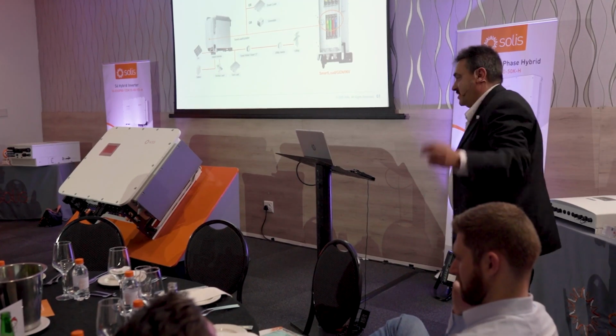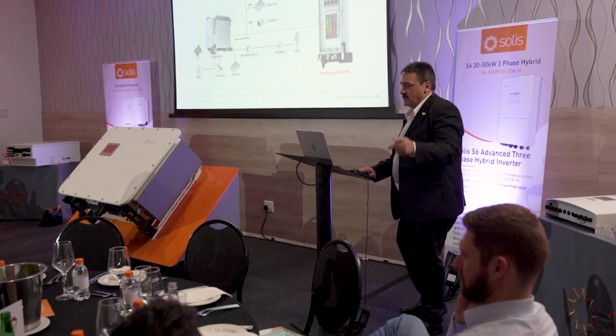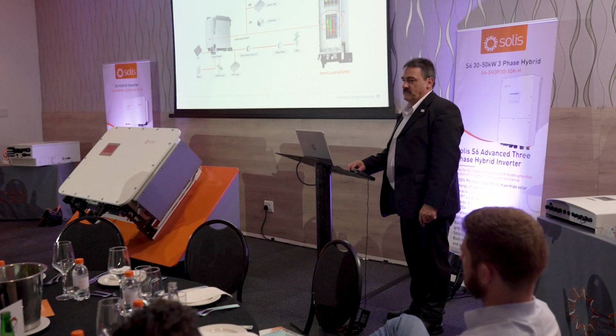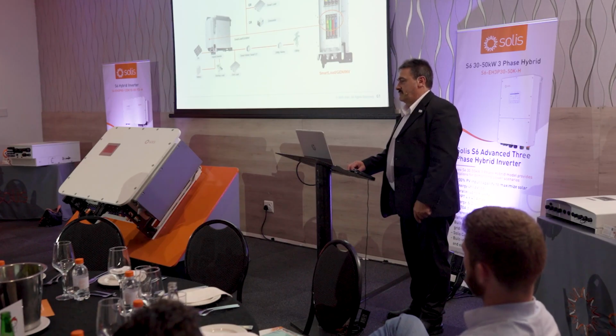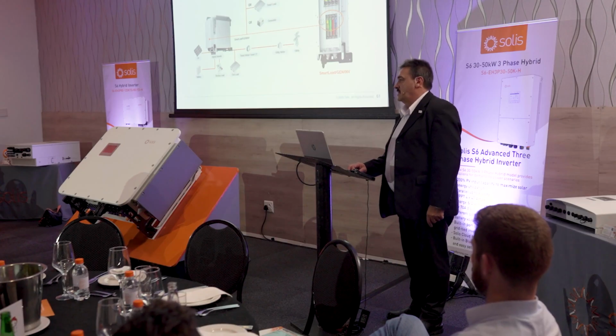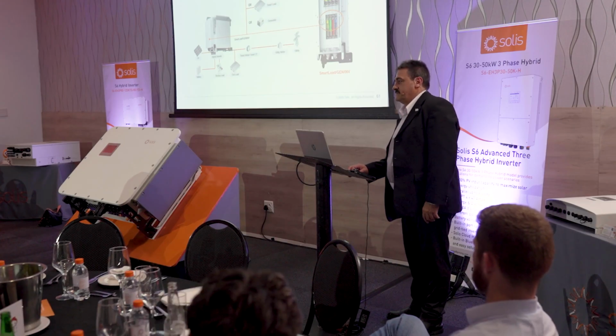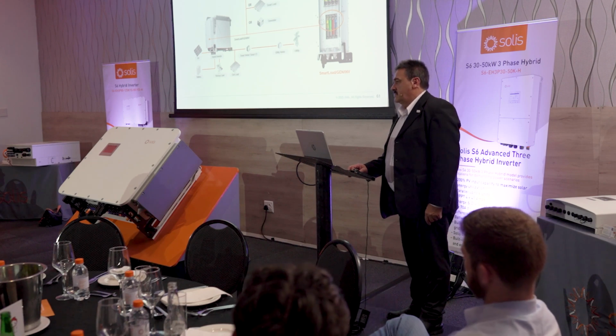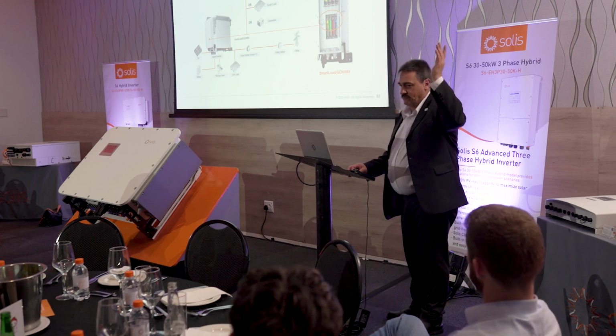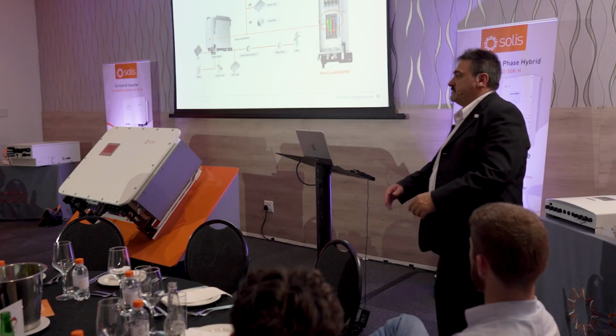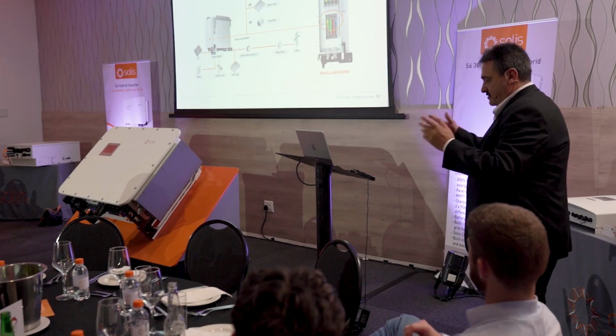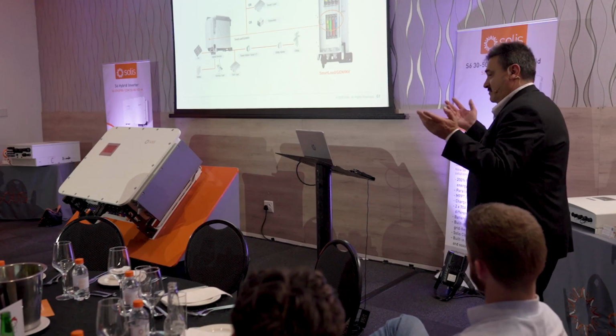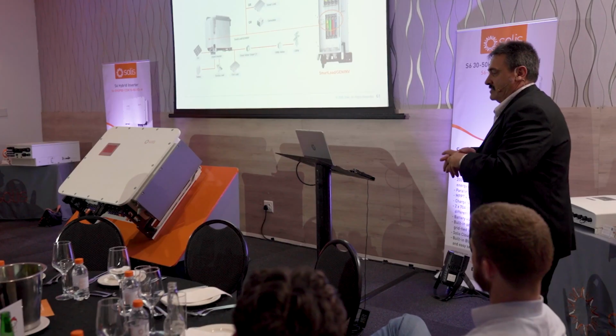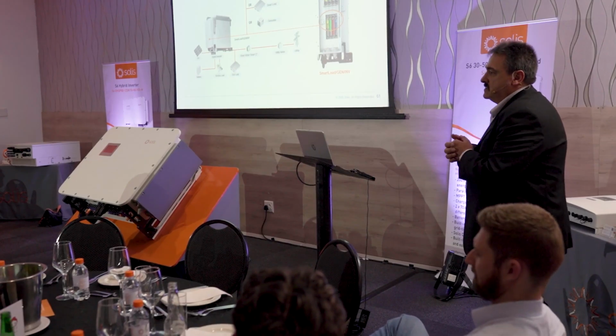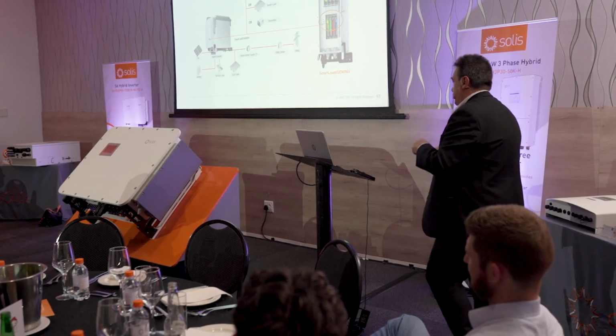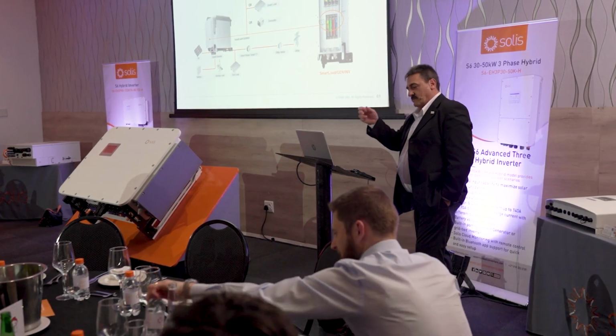I had a customer some time ago, it's not a big system, 40 kilowatt, but the home run was like 400 meters. And he did it with 2 different cables, so half of that was 50 mil aluminium and half of that was 50 mil copper. At the end of the day, the voltage drop was something like 29 volts, with an already increased grid voltage, so he was sitting at plus 253 volts. The inverter just wouldn't switch on. Eventually, when they changed it to a shorter run and sized the cable properly, the inverter worked fine, no problem. But it was also one of those cases where the customer says, my electrician has told me. The electrician must just do the math. It's just something that came to my mind. We get a lot of that.